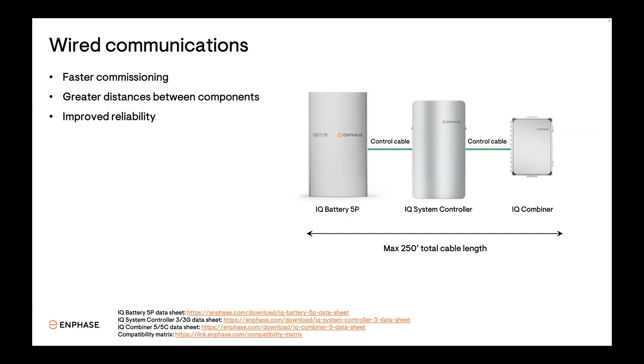As you can see, these are daisy chained together, and there can be up to 250 feet total cable length in any given system. So that, of course, gives you a lot more flexibility than we had before, where we recommended a maximum of 50 feet between components with Zigbee. Now it's 250 feet total cable length. So you can place the batteries on the other side of the garage easily or somewhere else on the house if there isn't space available near the main service panel where the combiner is located.